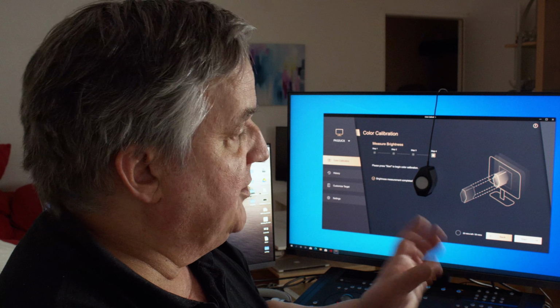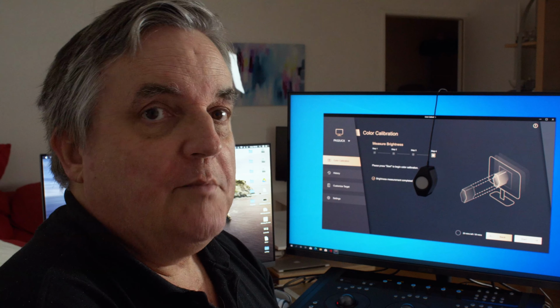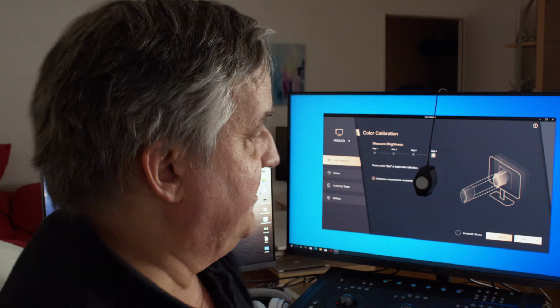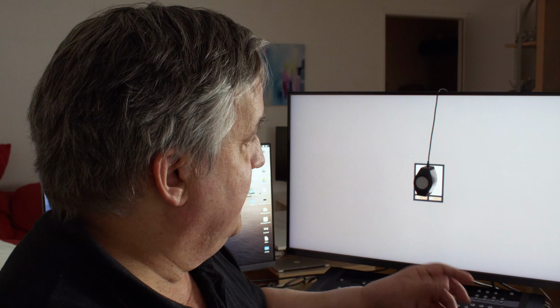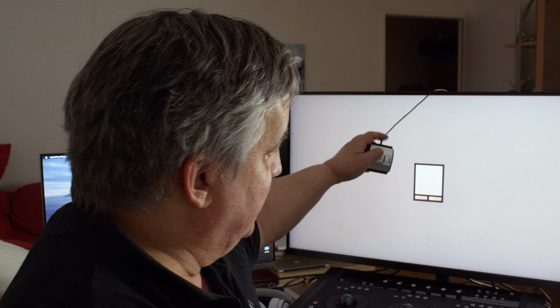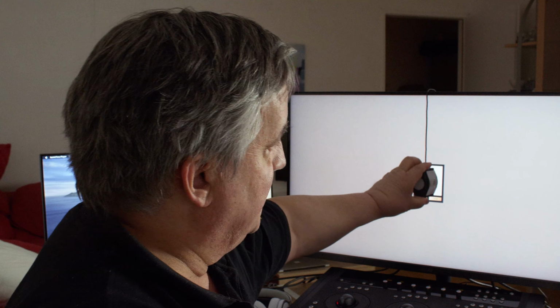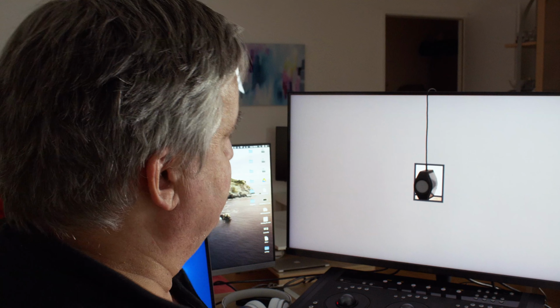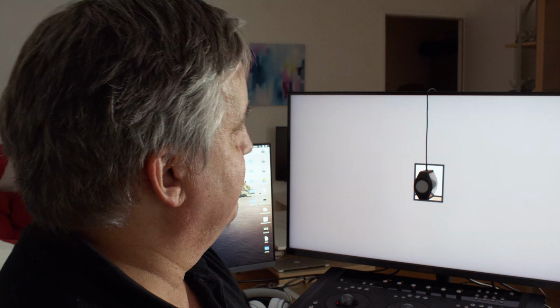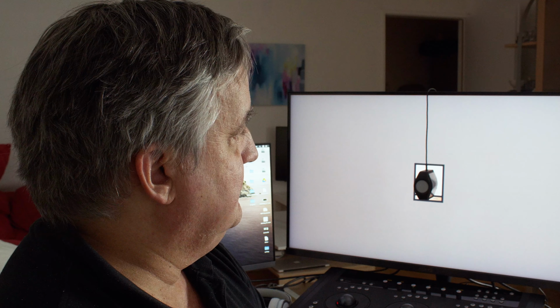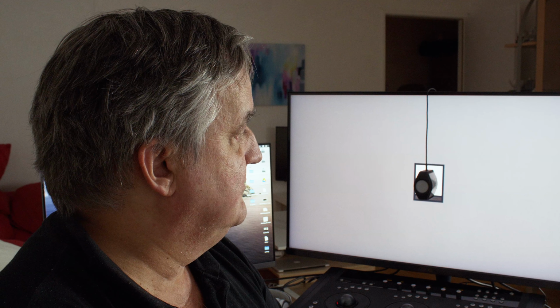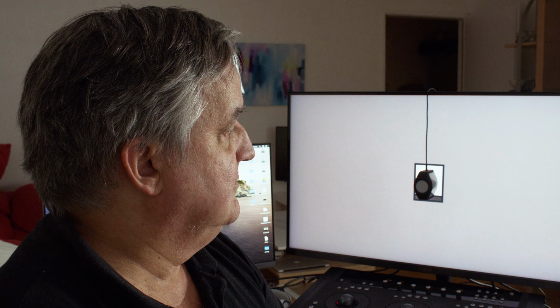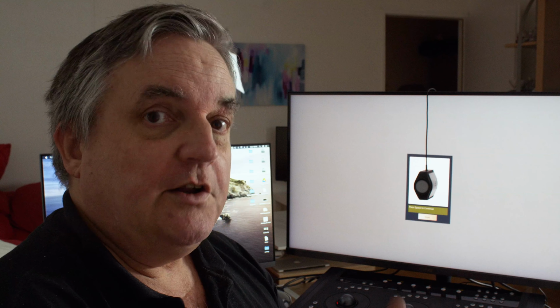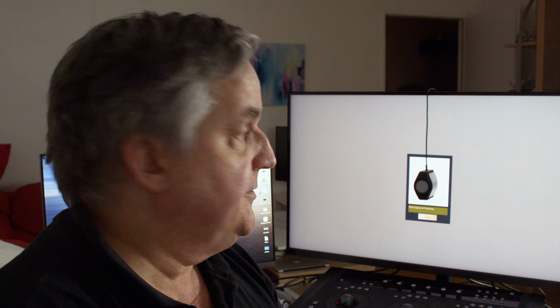Normally when you're starting the monitor for the first time, you should let it warm up for 30 minutes, and there's a little 30 minutes adjustment there. Once the warm-up has completed, then you will see this patch here that gives you the option to start or cancel the procedure. So what we do here, put our probe in the center, and then click on start. Now what this does, it does an initialization procedure. Once the initialization has completed, then it allows you to proceed to the rest of the calibration of the monitor.